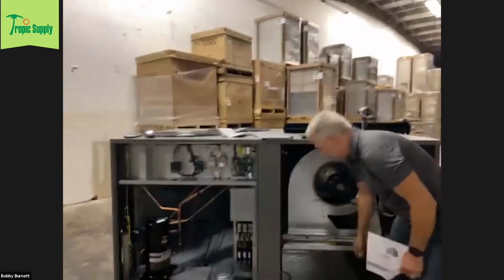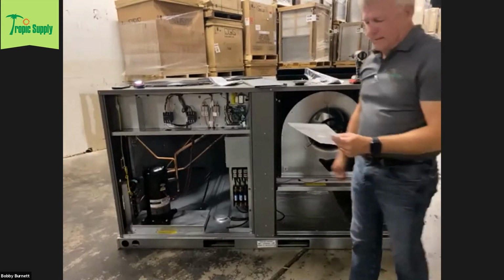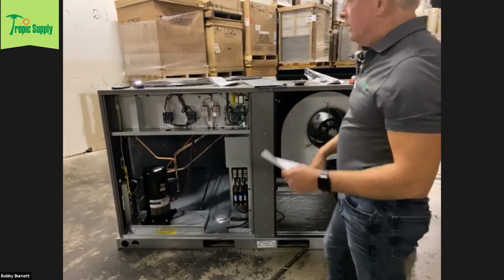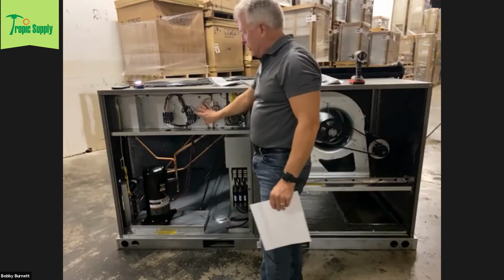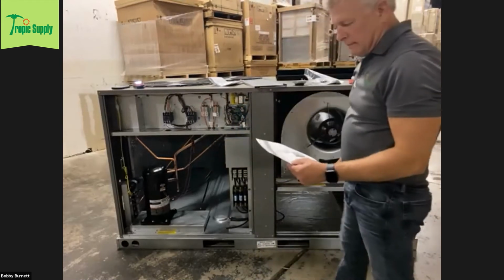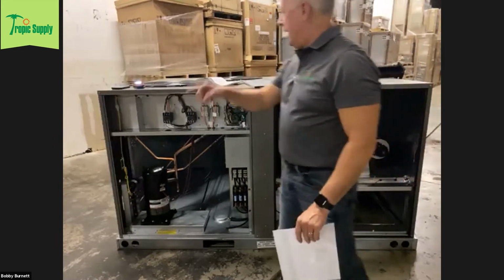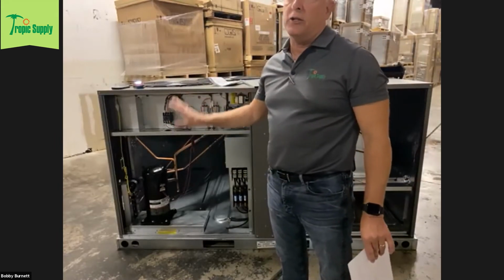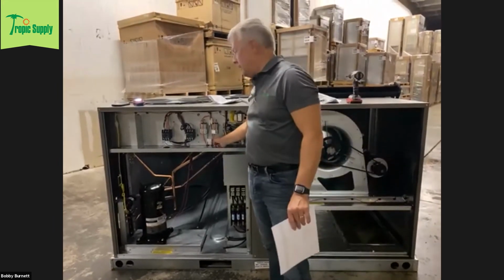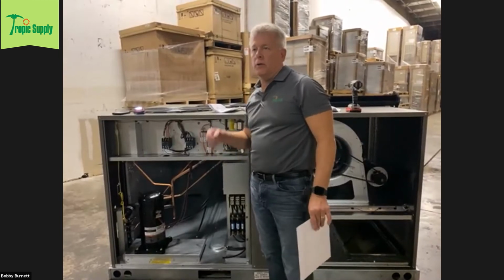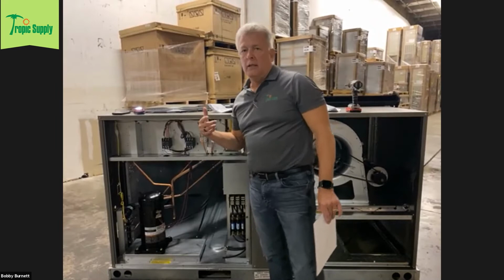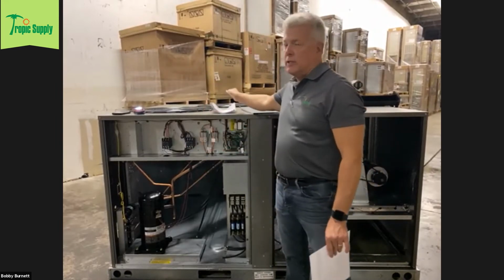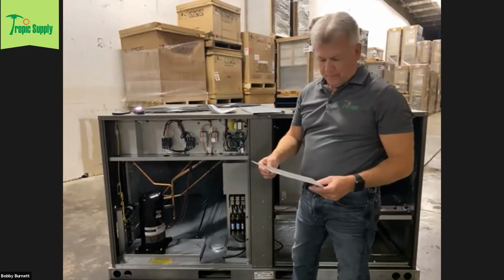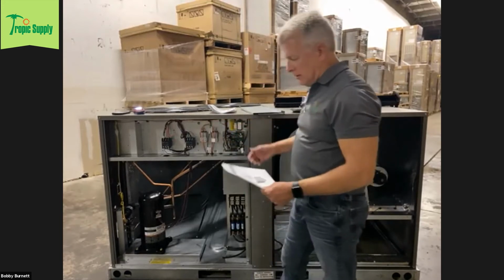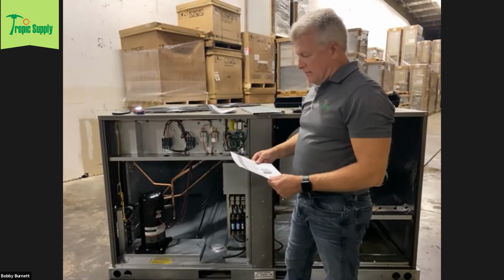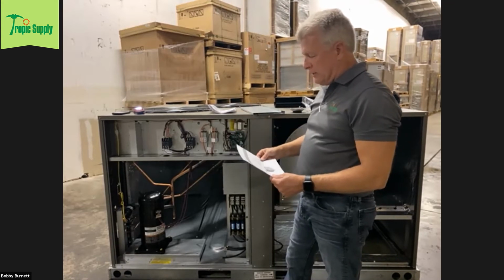So there's a 1-inch drip lip around here to help keep water from draining into the system. Your hinged access door and electrical divider plate are separate so you can access the electric without compromising the airflow. On the back of the panel you've got your electrical diagrams and charging chart, plus QR codes you can scan to pull up information on the unit, including product data sheets and installation manuals. If you're out on one of these units and the documentation is lost, you can scan the QR code to get all that information. Easily accessible, large access panel, external gauge ports, color-coded wiring, glued insulation.